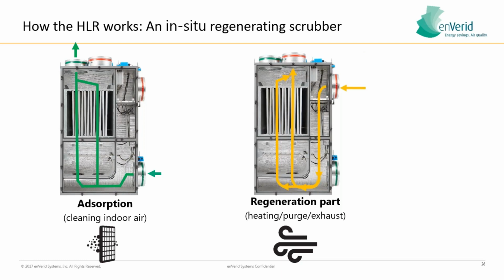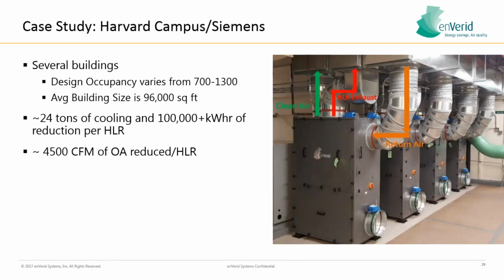And we are just regenerating these cartridges, releasing the total amount of CO2 that we're absorbing. These cartridges are so efficient at removing CO2 they can actually change weight throughout the course of a day. So in order to ensure that they have enough capacity to remove CO2, we heat them up to 130 degrees Fahrenheit and then exhaust that outside the building, okay? Very interesting. This is what makes our product incredibly unique, our ability to consistently remove CO2 and other contaminants without having to replace the cartridges very frequently. Just once a year cartridge change out as manufacturer spec, and you're still cash flow positive from an OpEx perspective, generally.